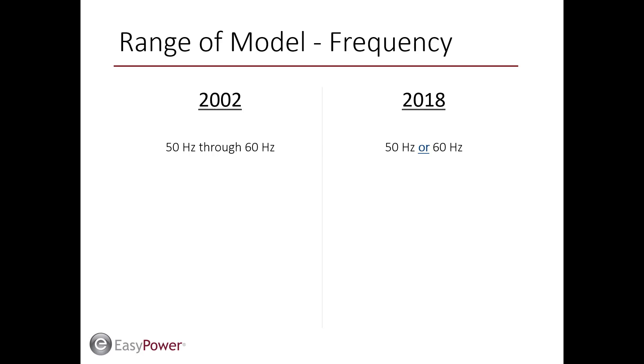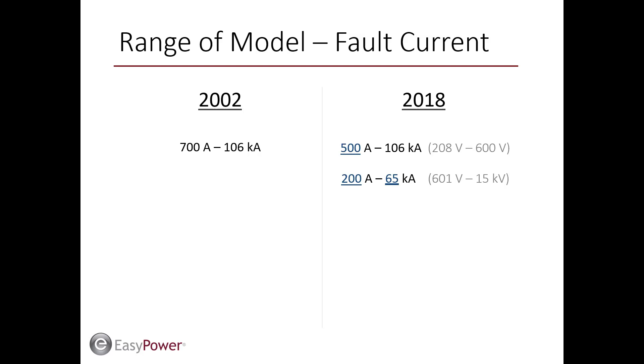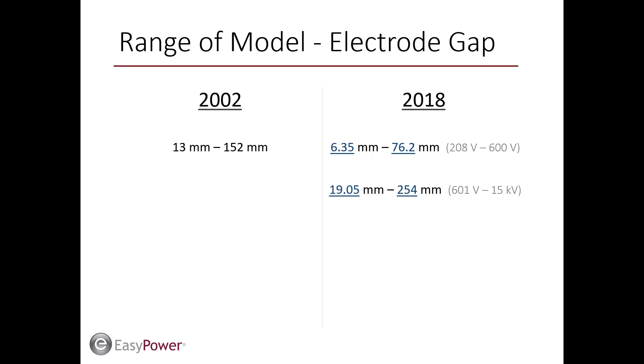The frequency range supported in the new standard is now explicitly 50 Hz or 60 Hz and no longer inclusive of frequencies between. This does not represent a major change as these calculation methods are typically applied at either of the specified frequencies. The range of bolted fault current supported by the new arc flash model is now dependent on voltage. The high end of the range sees a significant decrease for equipment greater than 600 volts. While a reduction to 65,000 amps is noteworthy, high voltage equipment does not typically experience fault currents exceeding this value.